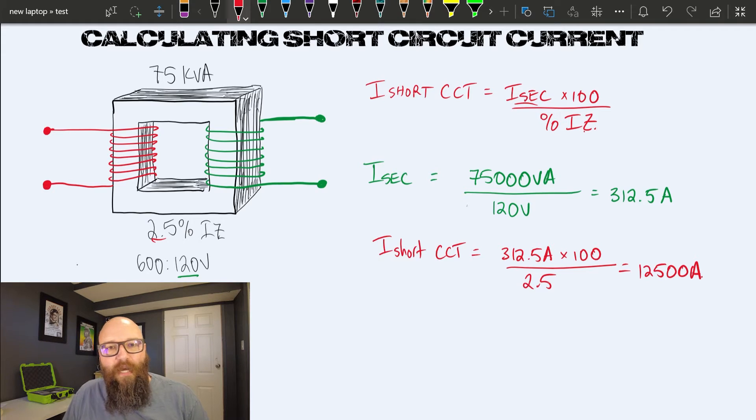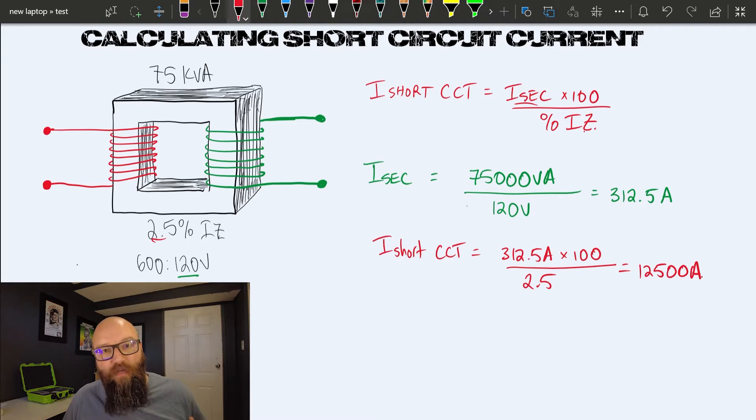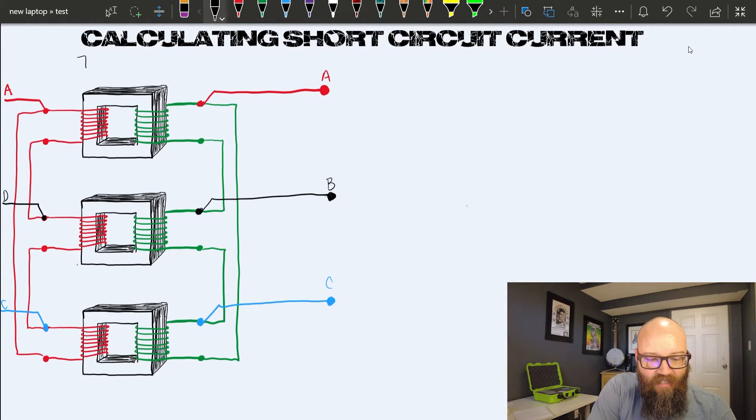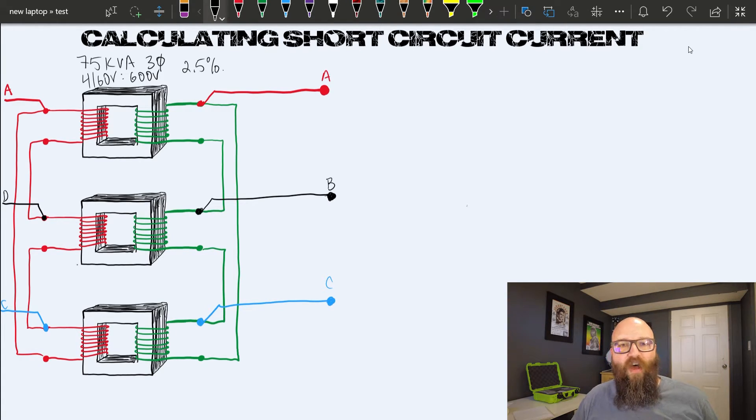Let's take this to a three-phase application. It's exactly the same formulas. The only difference is with the three-phase calculation, we need to be aware of when to use that root three number. Just like that, we've converted this to a three-phase bank of transformers. We're going to consider this one transformer with one total rating. This is a 75 kVA three-phase, 4160 primary volts stepped down to 600 volts on the secondary, with a 2.5% IZ.